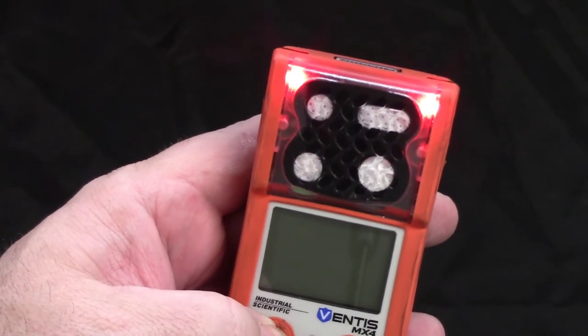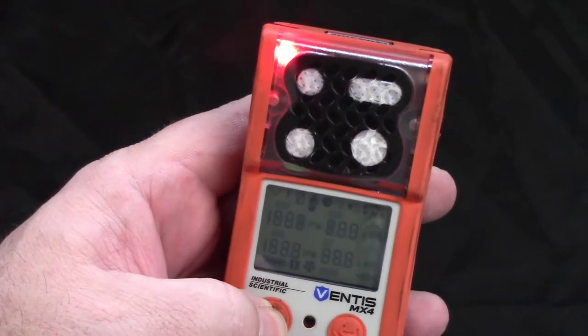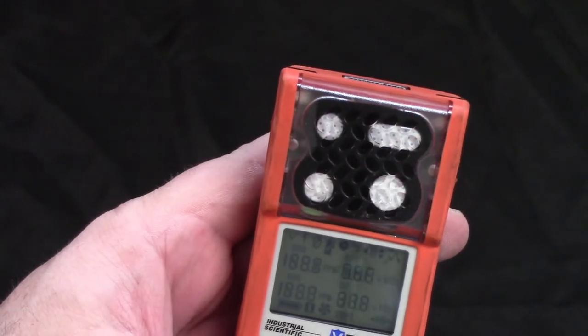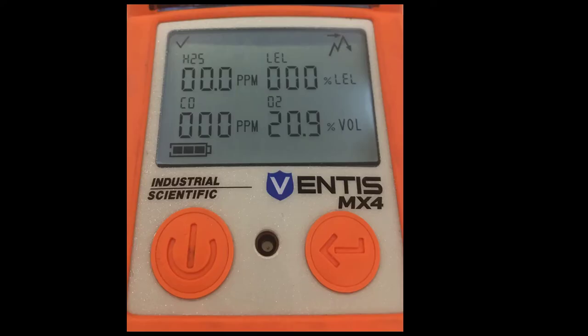In this video we're going to discuss the Ventis MX4. Start by pressing and holding the left hand power button to turn the unit on. As you turn it on it's going to beep and there's going to be a 20 second countdown as the catalytic bead heats up inside the LEL sensor.